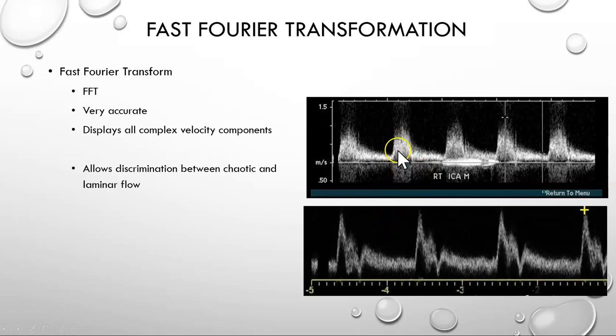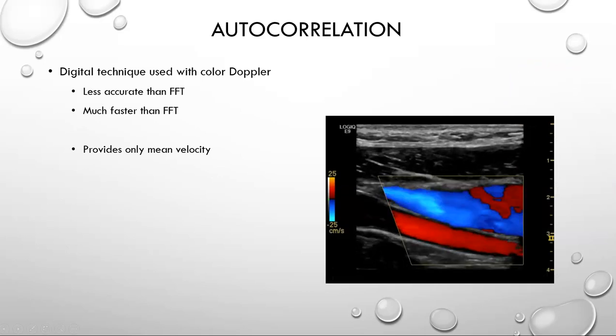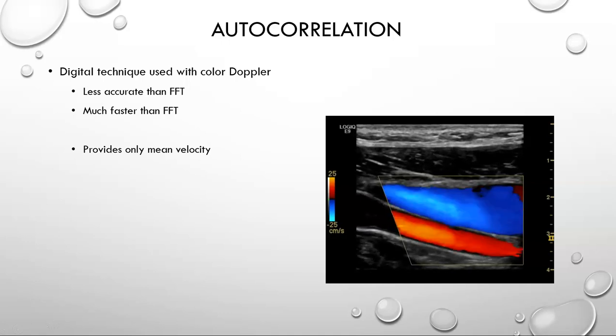FFT is very accurate and provides all complex velocity components, so we can see spectral broadening very well. In a normal laminar flow spectral display, during the systolic upstroke the velocity spectrum is very narrow — this is plug flow. When the heart relaxes, blood flow spreads out and we get wider velocity information characteristic of laminar flow. Above that, turbulent flow post-stenosis can be demonstrated. Autocorrelation is far less accurate than FFT but much faster, and provides only mean velocity information.